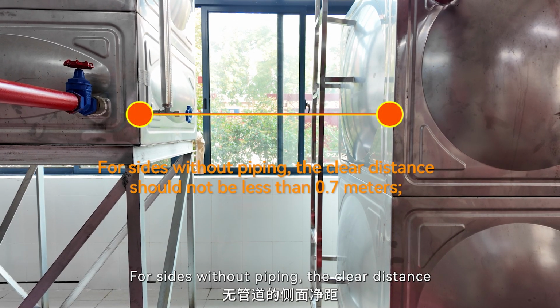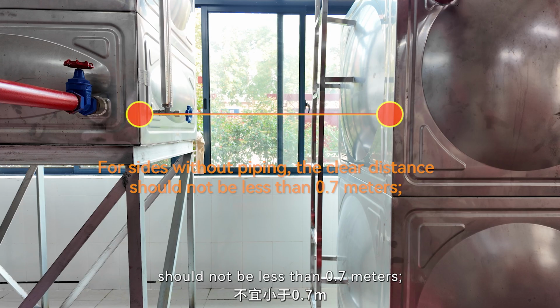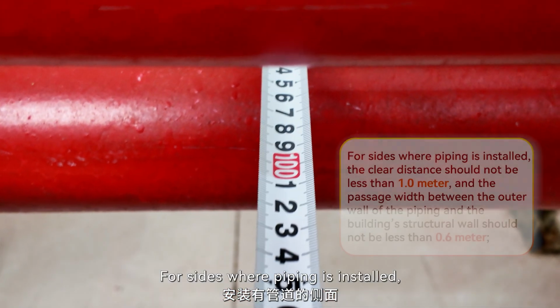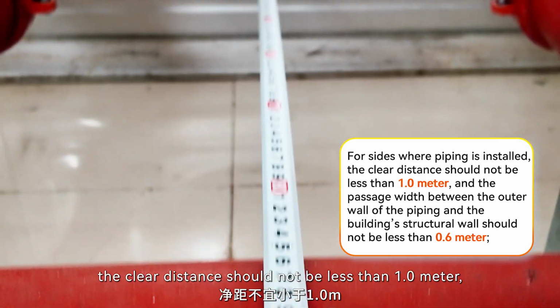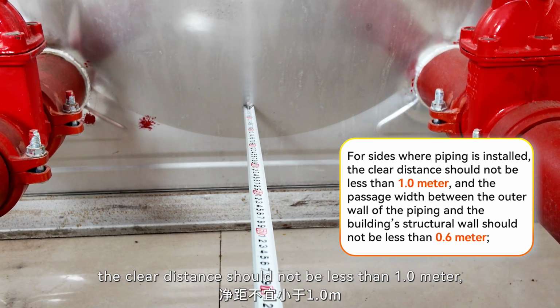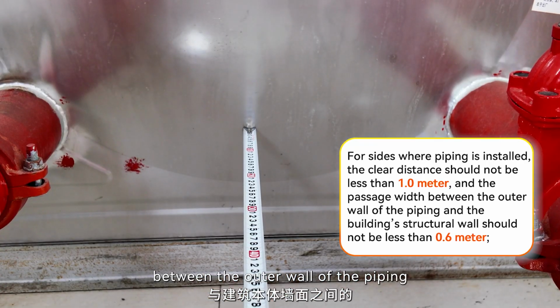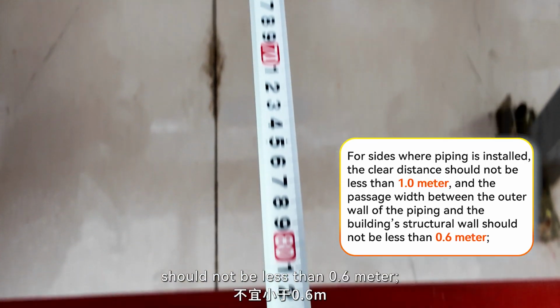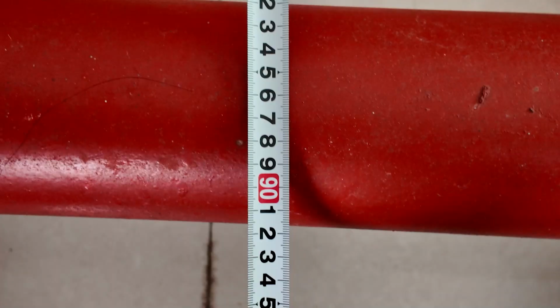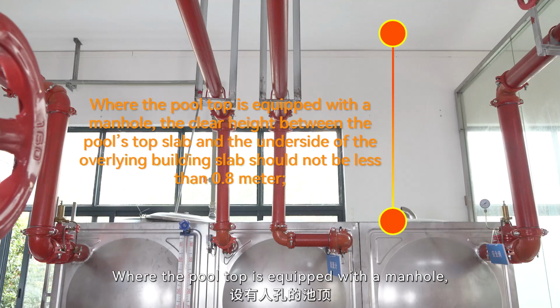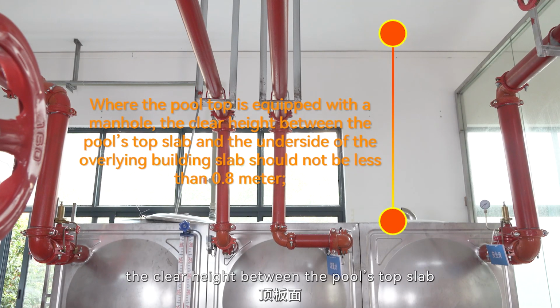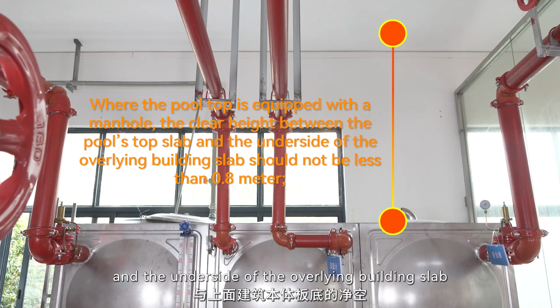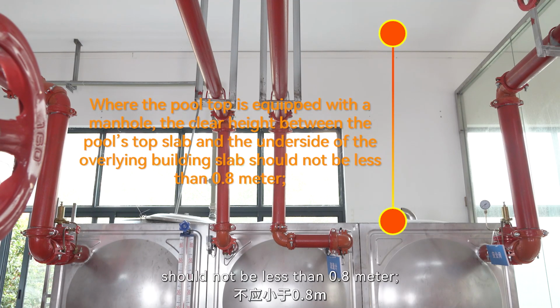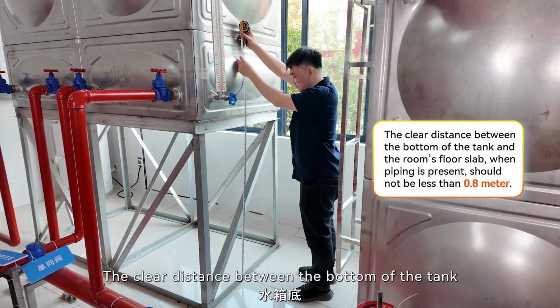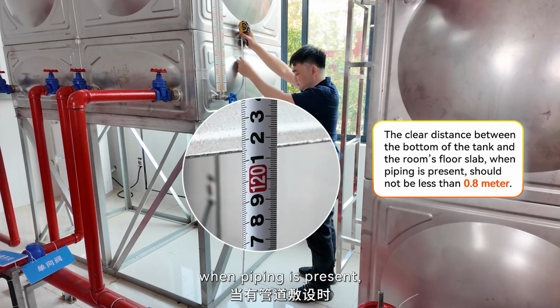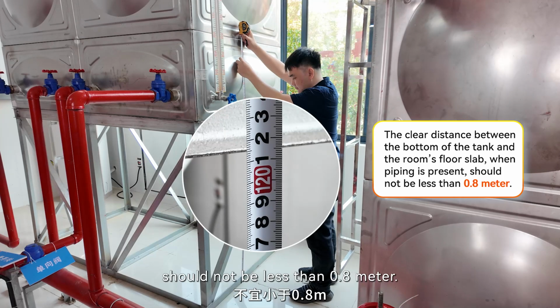For sides without piping, the clear distance should not be less than 0.7 meters. For sides where piping is installed, the clear distance should not be less than 1.0 meter. And the passage width between the outer wall of the piping and the building structural wall should not be less than 0.6 meter. Where the pool top is equipped with a manhole, the clear height between the pool's top slab and the underside of the overlying building slab should not be less than 0.8 meter. The clear distance between the bottom of the tank and the room's floor slab, when piping is present, should not be less than 0.8 meter.